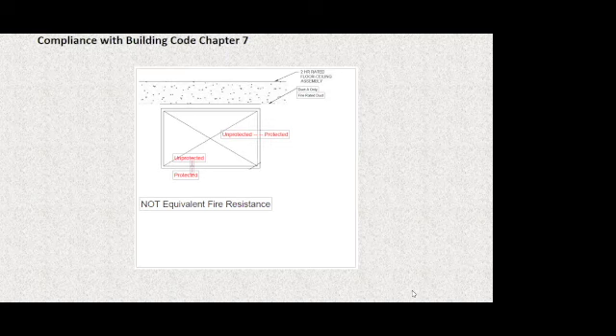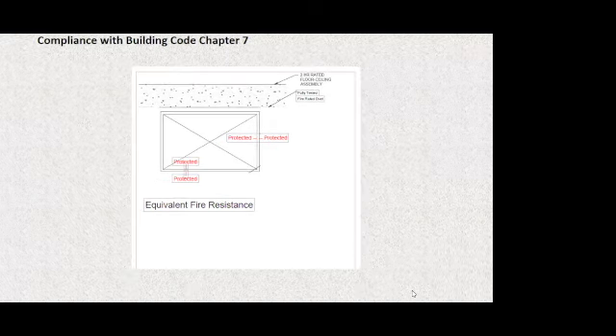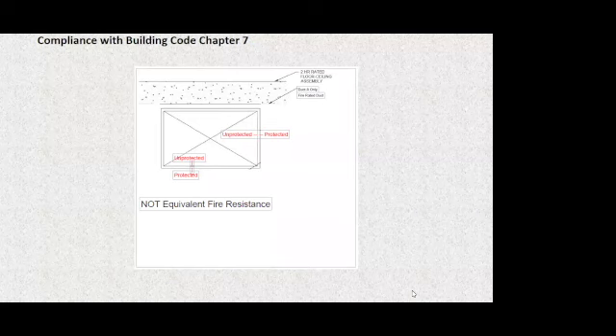It has only been partially tested. It is what they call duct A instead of duct B. Duct B is fully tested, fire inside, fire outside, both sides. Using the lower of the two, the hourly rating is the assembly rating. That's what the code tells us to do. If we only test part of it, we didn't do our jobs. And if nobody's checking, then it slips through the cracks. And I cannot tell you how many jobs I have walked into in my 30-year career where it almost slipped through the cracks.